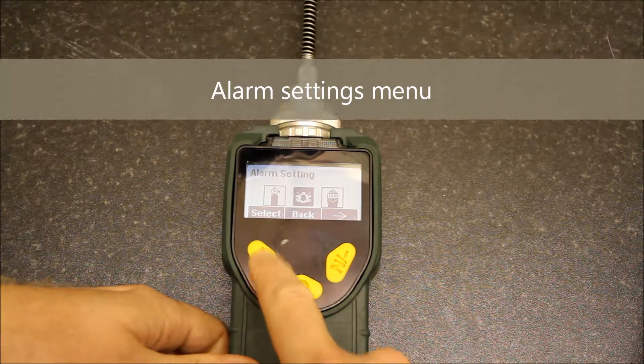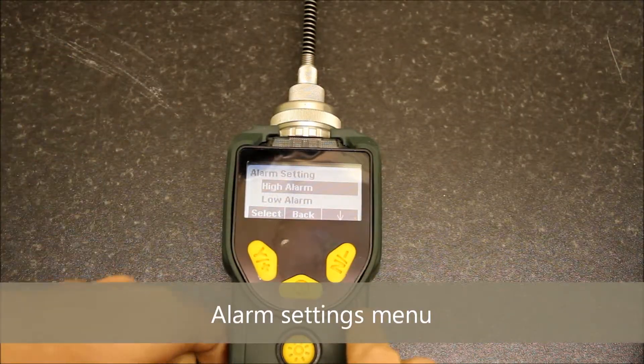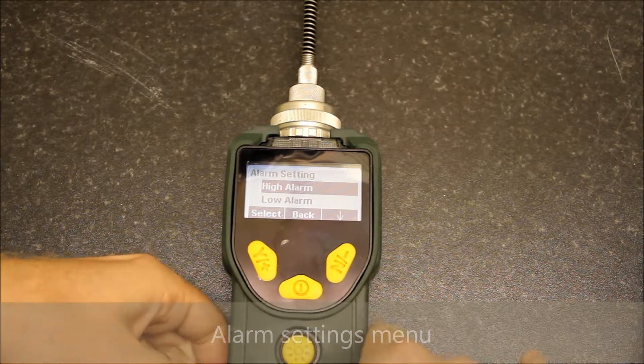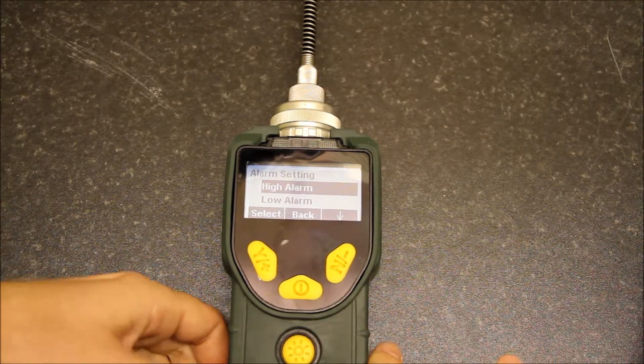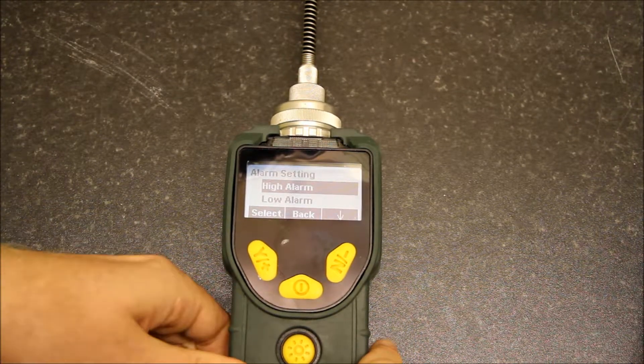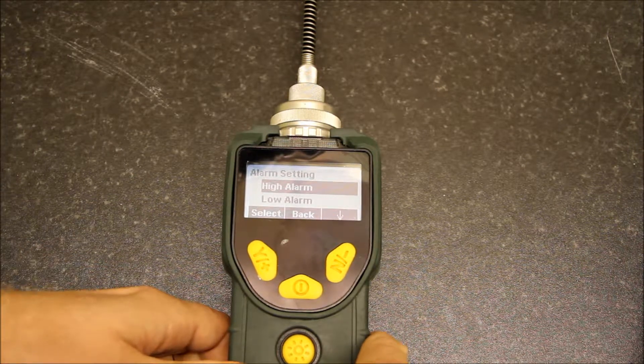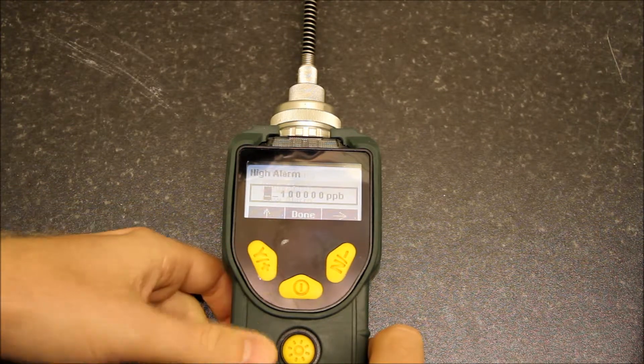If we go to the alarm settings and press yes, we can now change alarm values here. This is useful for headspace analysis for the environmental sector because you don't want alarms going off constantly. If we press select for high alarm, you can see readings are displayed in ppb but this is set at 100 ppm.